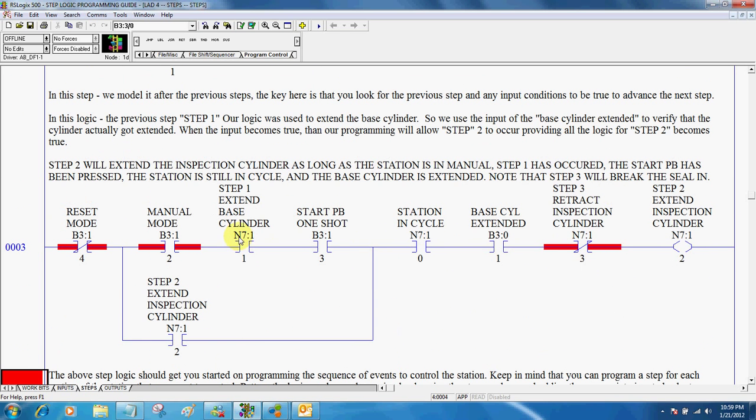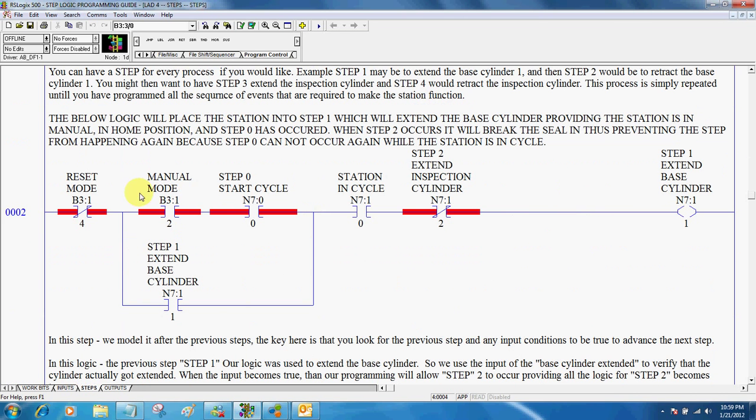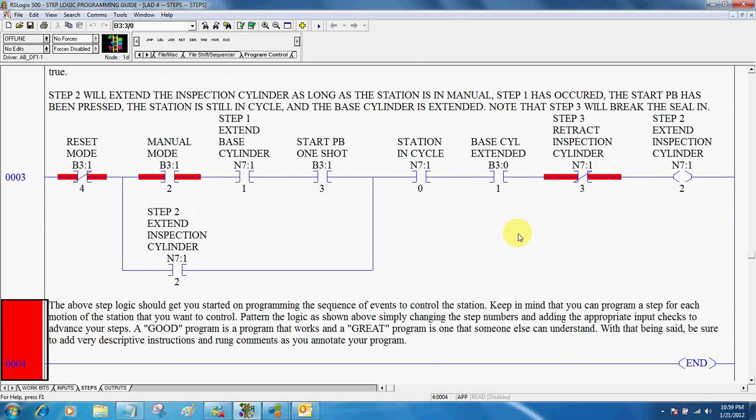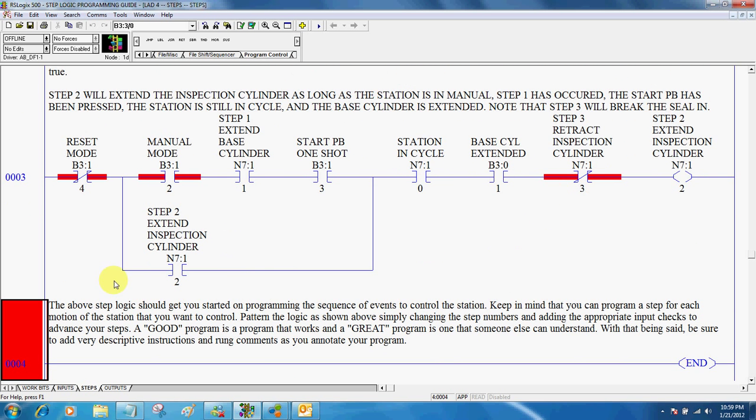Step one must have happened, and then we look to see that it actually occurred. So again, manual mode, step zero, we're in cycle. Step one is extend the base cylinder. This would become true, and when this becomes true, and the base cylinder actually become extended, then step two would occur. So all you would do is continue to model your logic after the steps above, creating a step for every position or every movement that you want to monitor and occur.